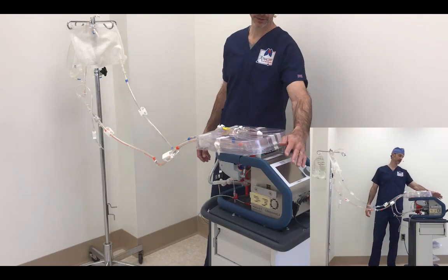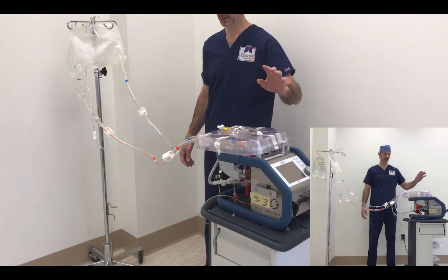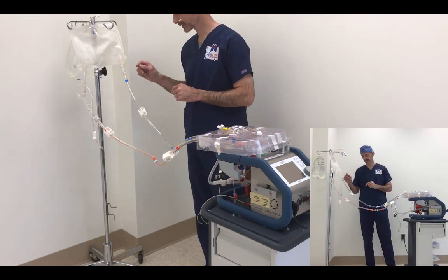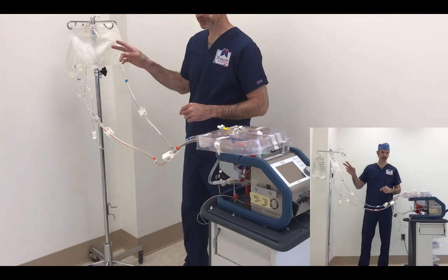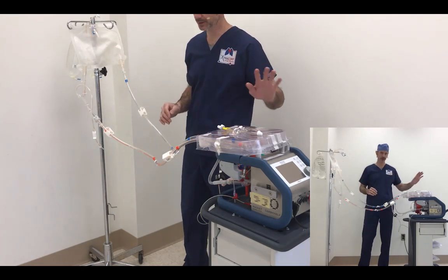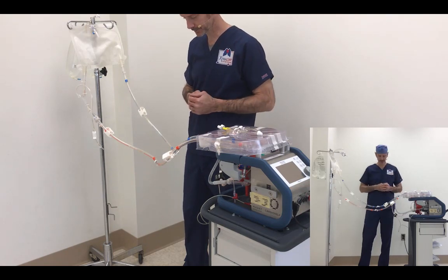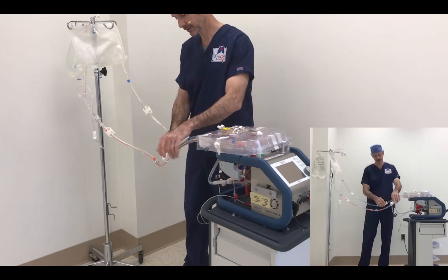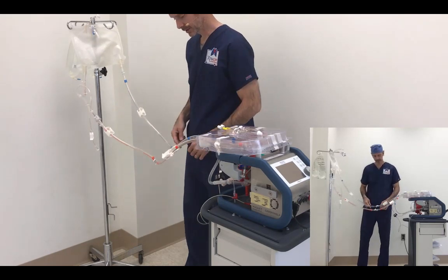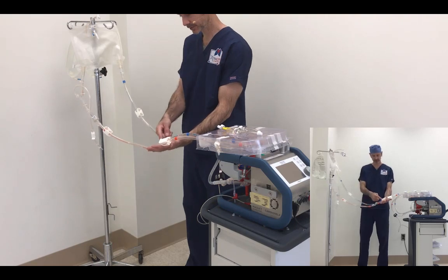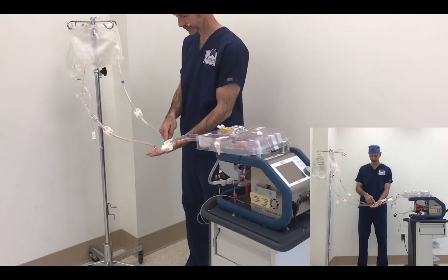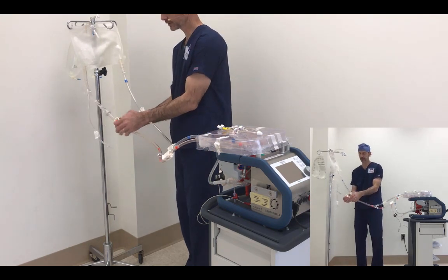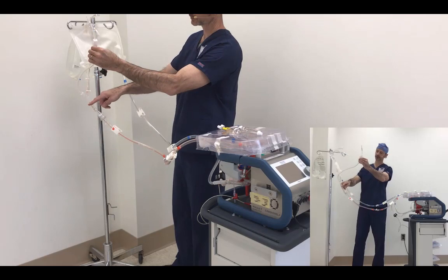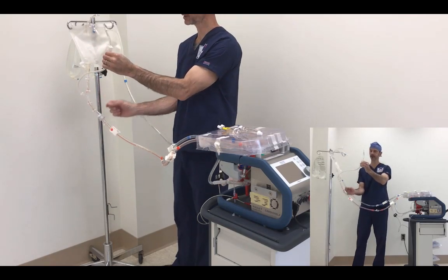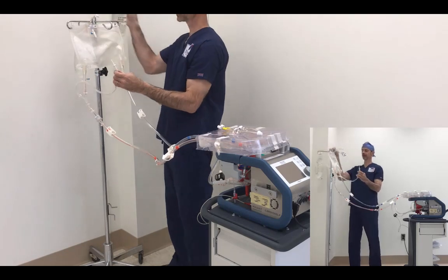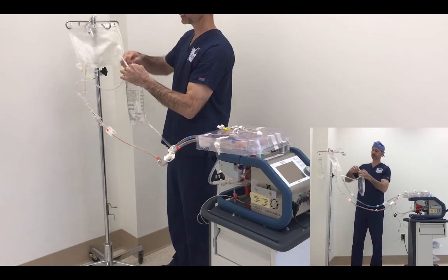Now I have some things to do electronically to turn this on and zero some stuff, but that takes a little bit of time, just as running these bags in takes a little time. So why don't we spike 2 bags and get some fluid accumulating over here, and then while that's running, we'll go over and turn on the electronics. So before you add any fluid to this, clamp these quick connects. Clamp these thumb clamps that are on the arterial and venous lines. There's another set of those after the quick disconnects. I'm going to clamp those as well. There's a spike hanging off the arterial side above a one-way valve, and we can spike this bag and let this fluid run in.